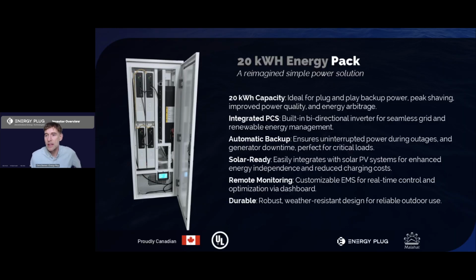And so here, if we look more at the 20 kilowatt hour energy pack, you can see on the left there it's 4 vertical batteries. Those are 5 kilowatt hour LFP modules. Those are what will be produced in our factory at Vancouver Island. And so it's meant to be plug and play. This is for backup power, peak shaving, energy arbitrage, for example. It's got an integrated PCS, or power control system, AKA inverter, and this is a bidirectional inverter that allows power to go in both directions, and it's controlled externally via our EMS system or programmatically from the EMS as well. So it can be automated, again, so automated backup right there.